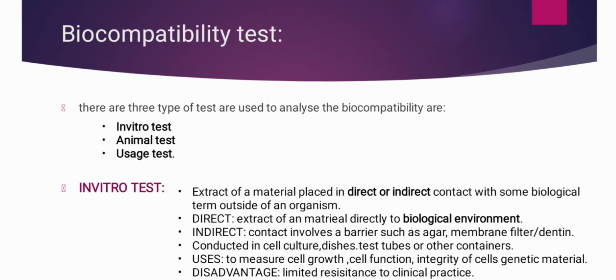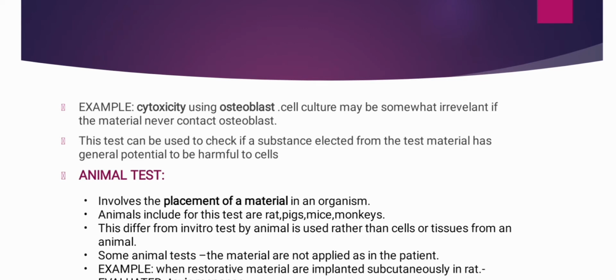Used to measure cell growth, cell function, integrity of cells, genetic material. Disadvantage: limited relevance to clinical practice. An example: cytotoxicity using osteoblasts. Cell culture may be somewhat irrelevant if the material never contacts osteoblasts. This test can be used to check if a substance eluted from the test material has general potential to be harmful to cells.